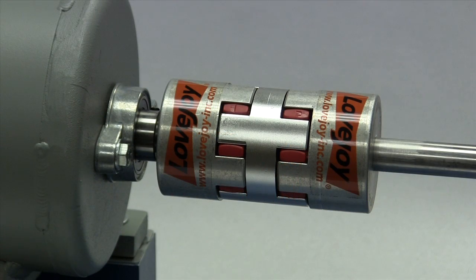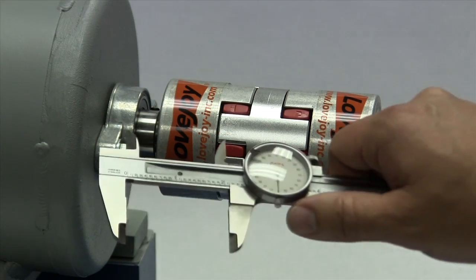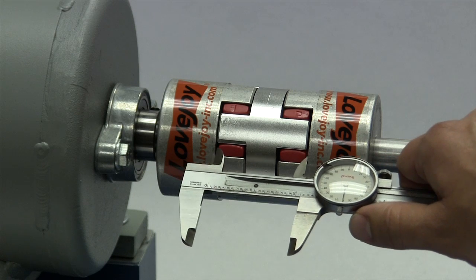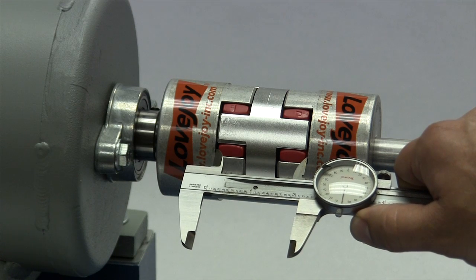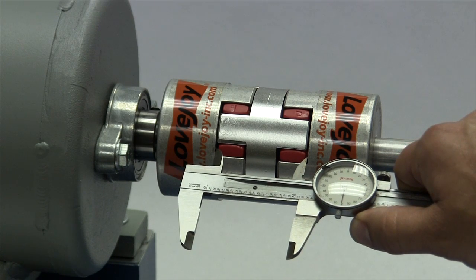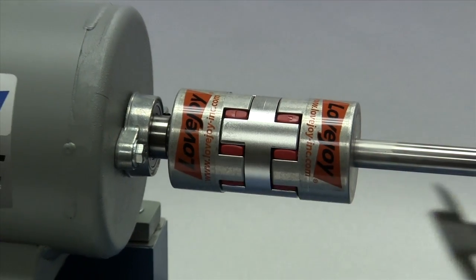At this time, check the shaft separation by measuring between the faces of the hubs. Compare this measurement with the BSE dimension in the installation guide for the particular size coupling you are installing.